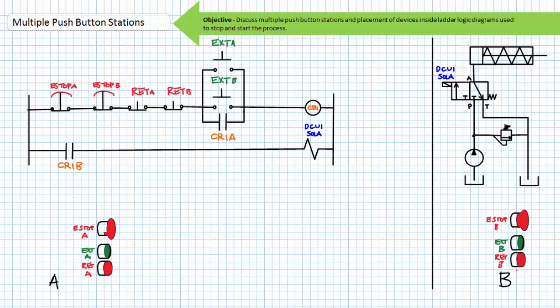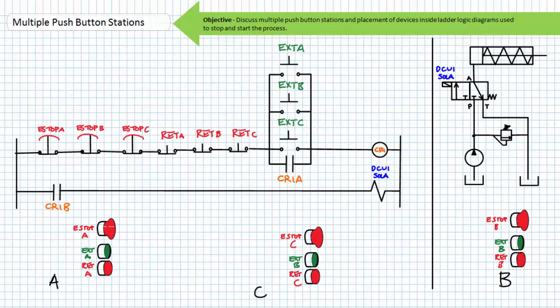Consider troubleshooting scenarios in which any one of the e-stops or retracts developed an inadvertent open — the cylinder would never extend. Voltmeter checks at various points in the pilot circuit would show all voltage being dropped across the unintended open, counter to expectations. In the ready state, ordinarily all voltage would be dropped across the parallel combination of extend buttons and the holding contact. If e-stop B was open, all voltage would be dropped across e-stop B, with elements between those points floating and not electrically connected to the circuit. Consider another troubleshooting scenario in which any one of the extends inadvertently sticks closed — the cylinder would always extend, provided all the e-stops and retracts were closed.